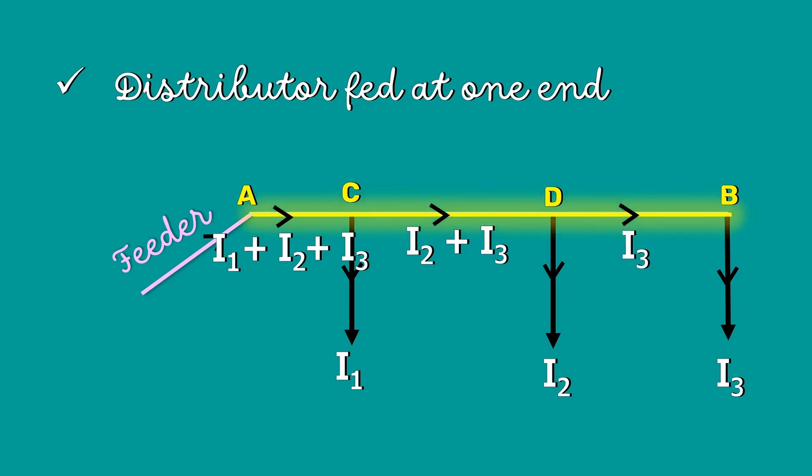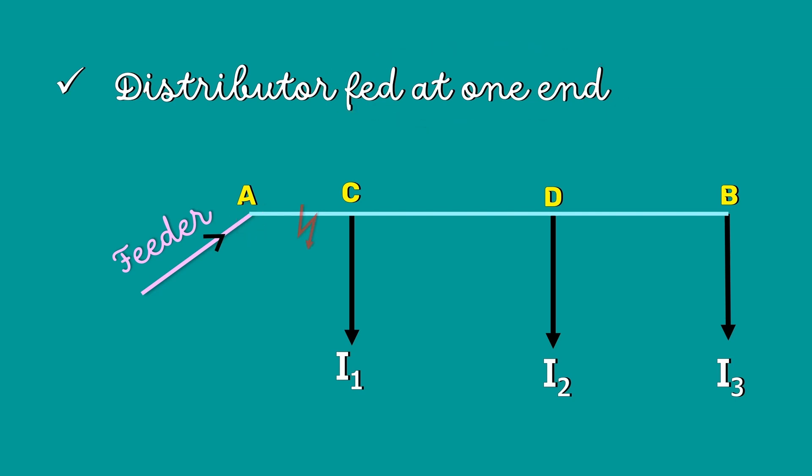Now, look at this distributor AB. The current in various sections of this distributor keeps on decreasing. This also means that the minimum voltage occurs at the load point B. Since the distributor is fed at only one end, in the case of fault, the continuity of the supply is interrupted.